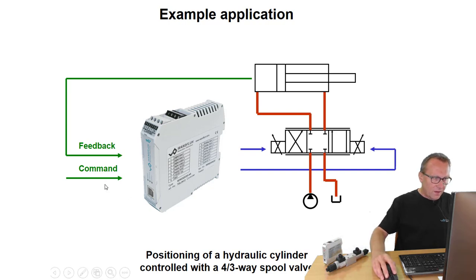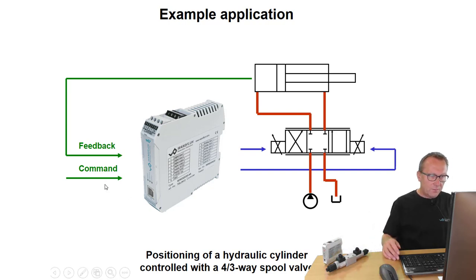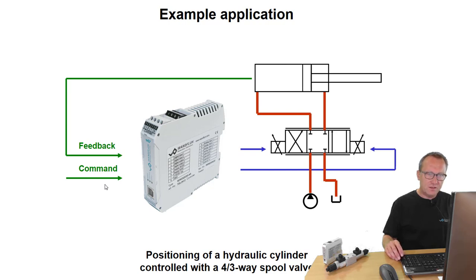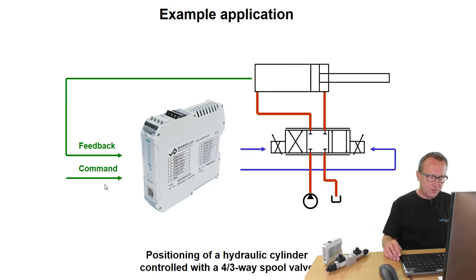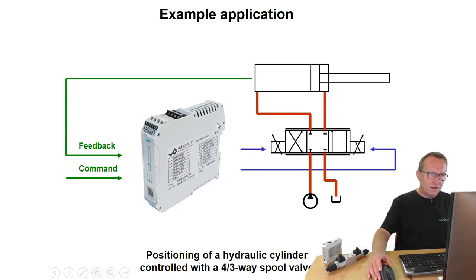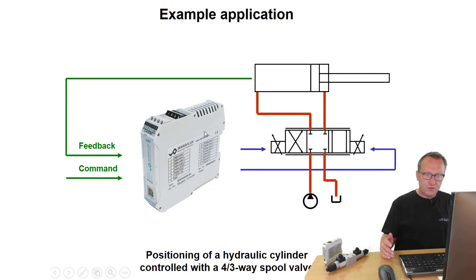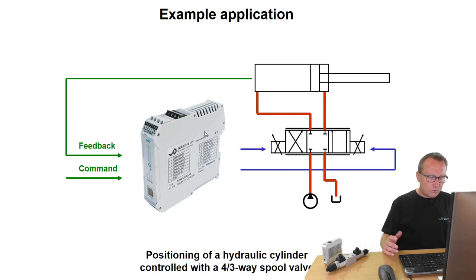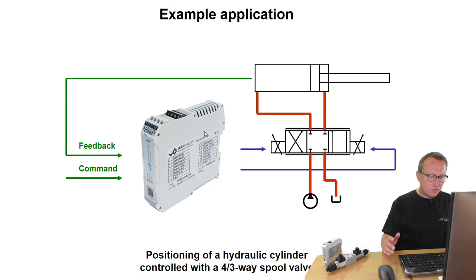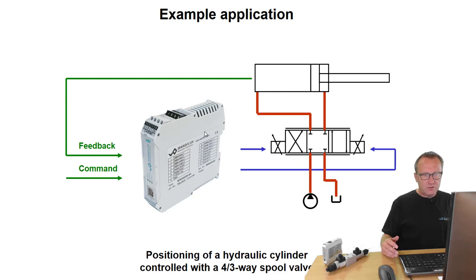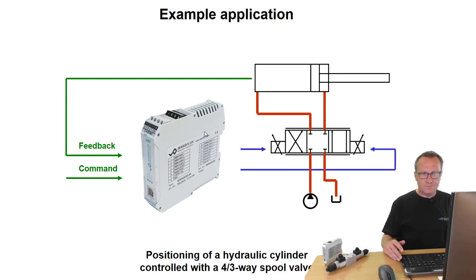With the command value I can define a position, and then the cylinder will move with a preset speed to this position. Through the position sensor, the electronic card gets the actual position of the cylinder. If the cylinder wants to move due to any change of temperature, pressure, or load, the electronic card readjusts to keep the command position.